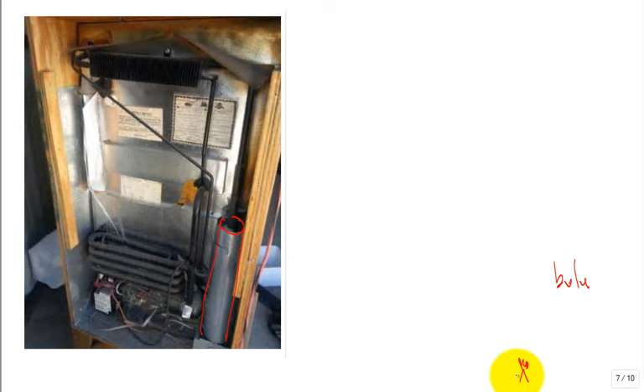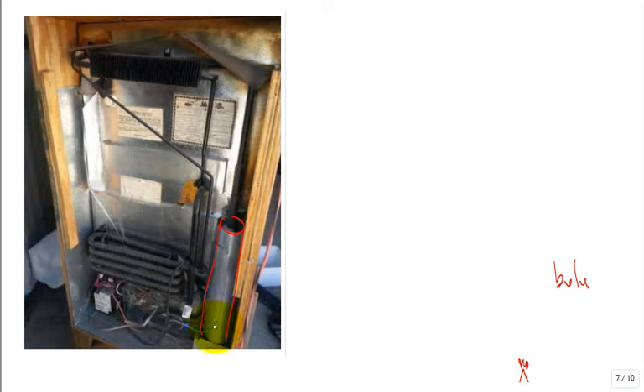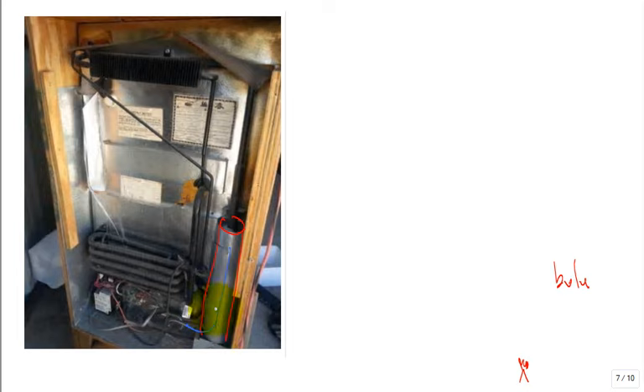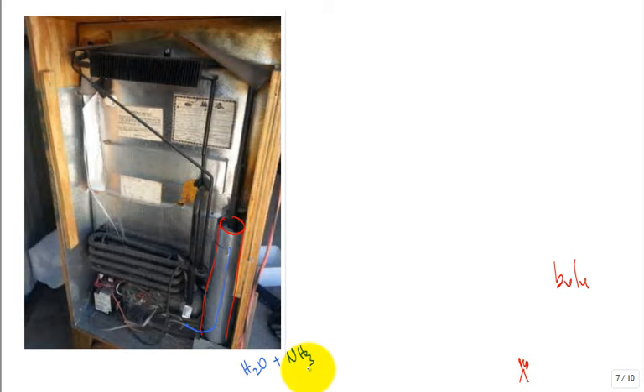At the bottom of the boiler, when you're running in propane mode, it's burning flame. There's some fluid coming in here and it gets hot. It's like a percolator in an old-fashioned coffee maker. The heat is real intense right on the bottom and it spurts up, pops it up. You have water, but you also have something absorbed in the water, NH3, ammonia. That's our refrigerant that's eventually going to get to the evaporator coil. The water doesn't provide the cooling, the ammonia does.